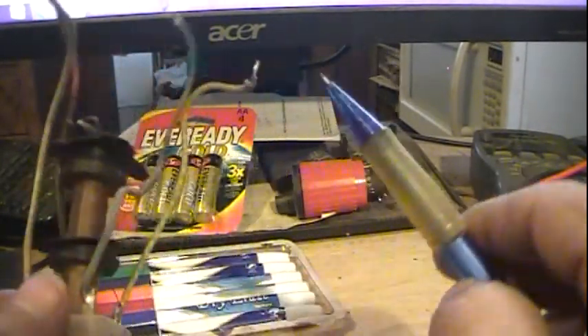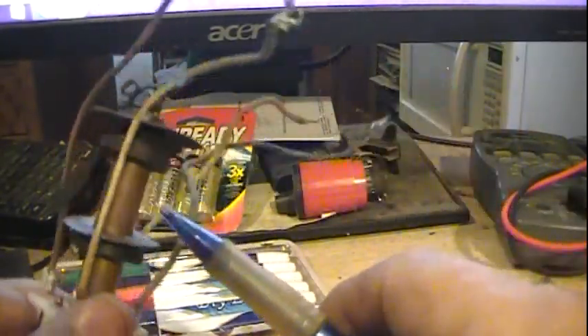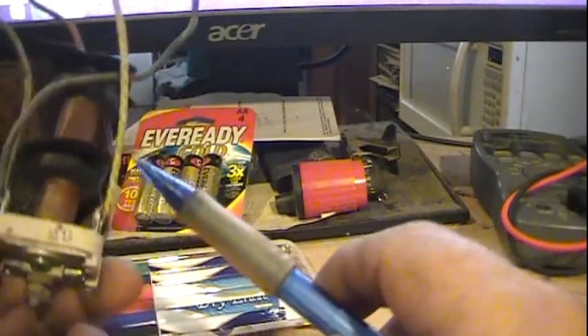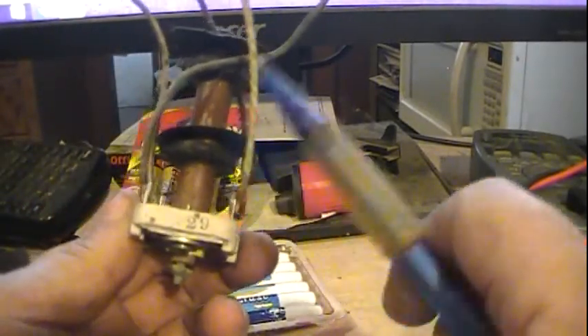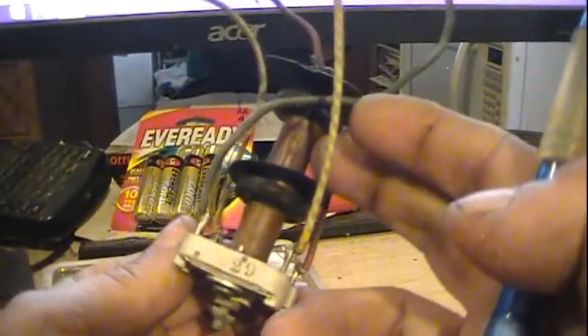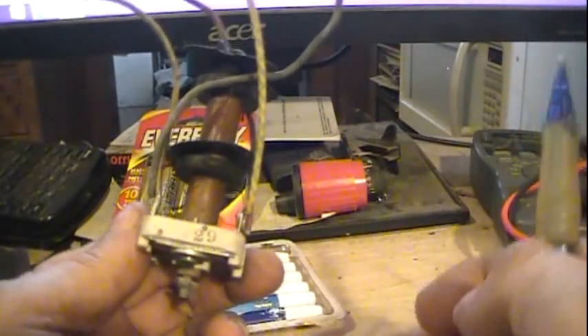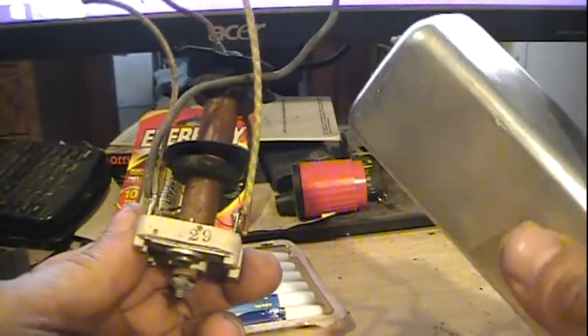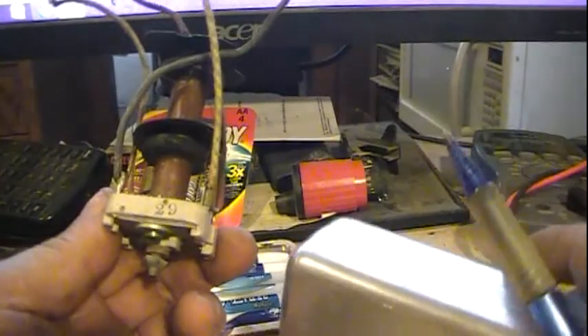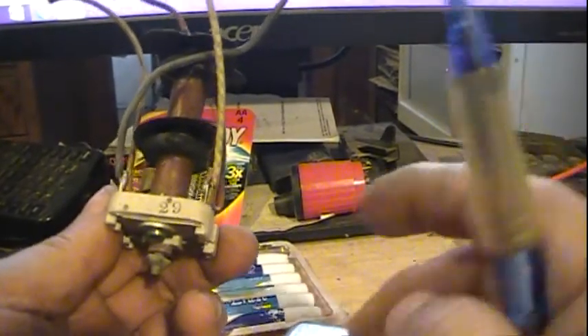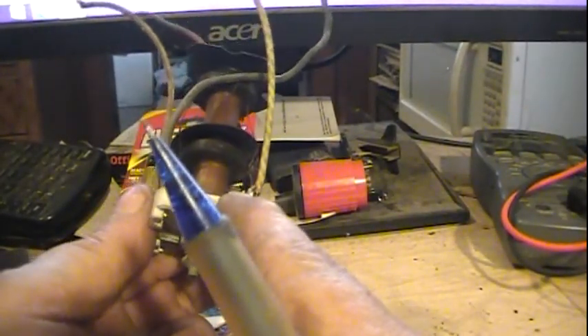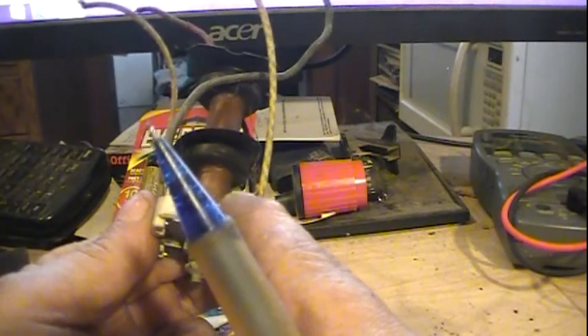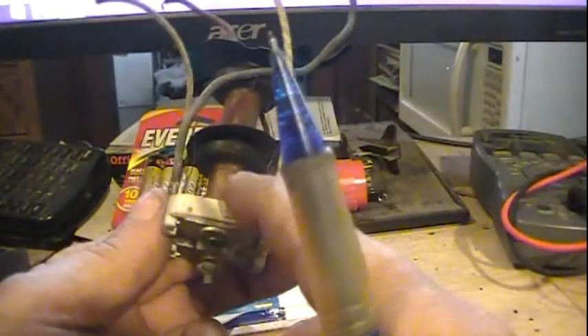It shouldn't shut it completely down unless there's a short, which is always a possibility, especially on the grid side, where maybe one of these leads is shorted to the can. That's a slight possibility, but in either case, you can check real quick and see if you can get it operational just by removing the can.